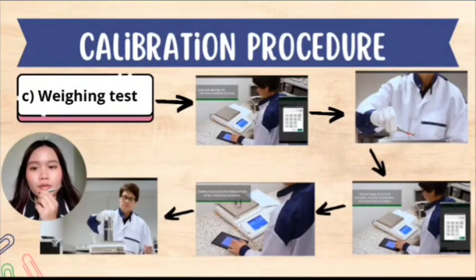Next, we have the weighing test procedure. The purpose of a weighing test is to test the accuracy of the weighing instrument throughout its whole range in several steps with increasing and decreasing weights. In this procedure, start by zeroing the instrument without any load, and then set the load of the first test point, wait for stabilization, and then record the indication. After that, continue increasing the loads through all the increasing test points. Typically, 5 to 10 different loads are used. And once the maximum load is recorded, start decreasing the loads through the decreasing test points.